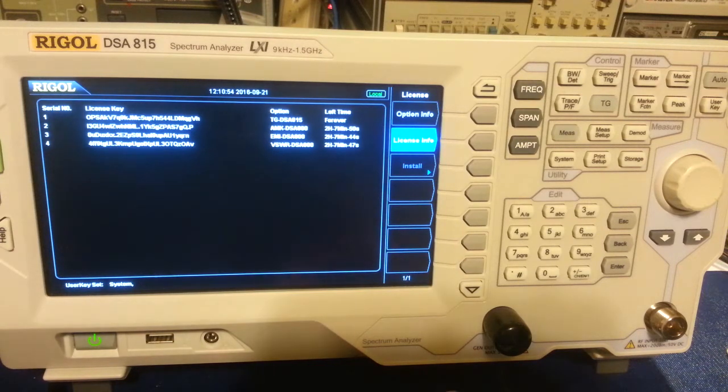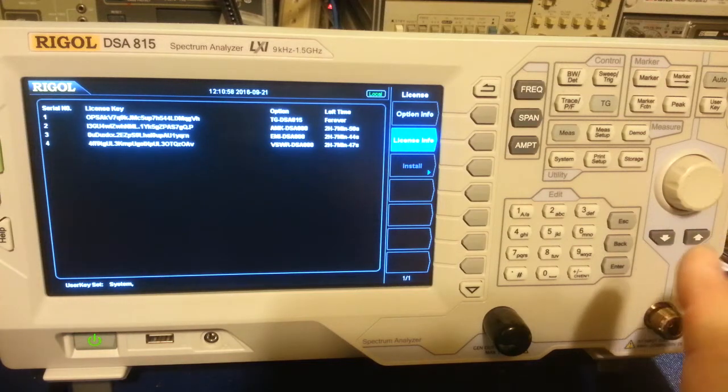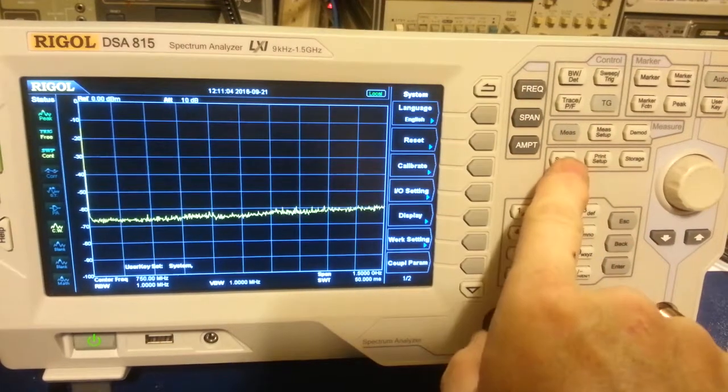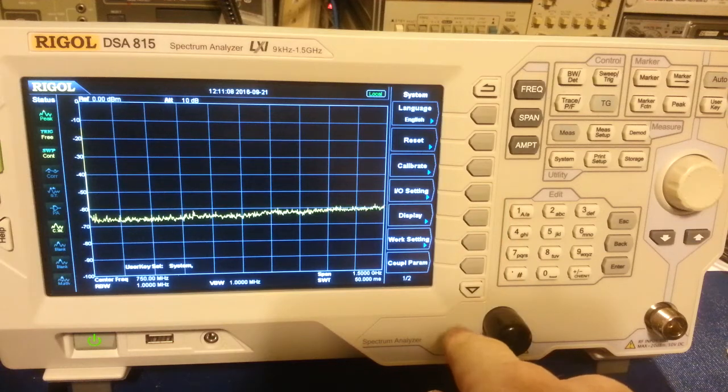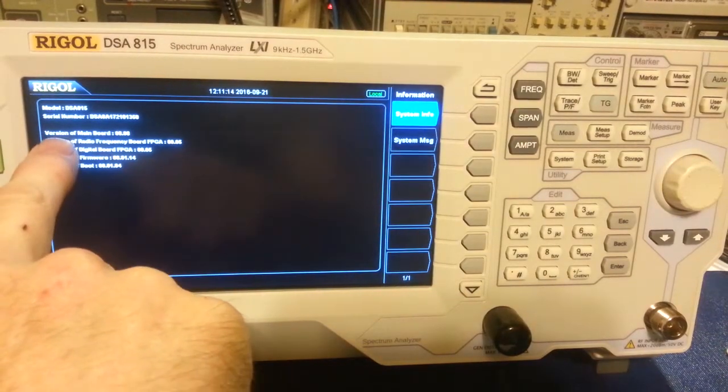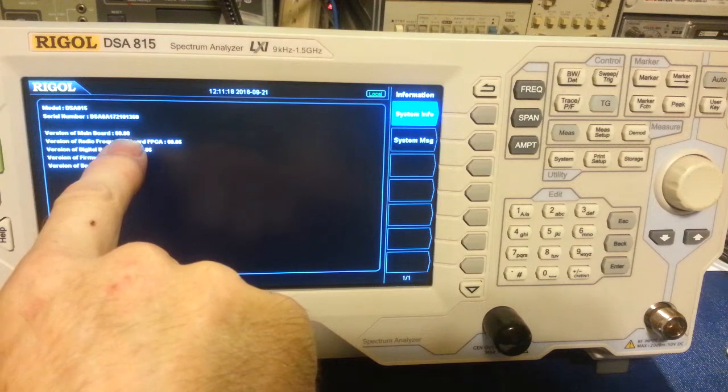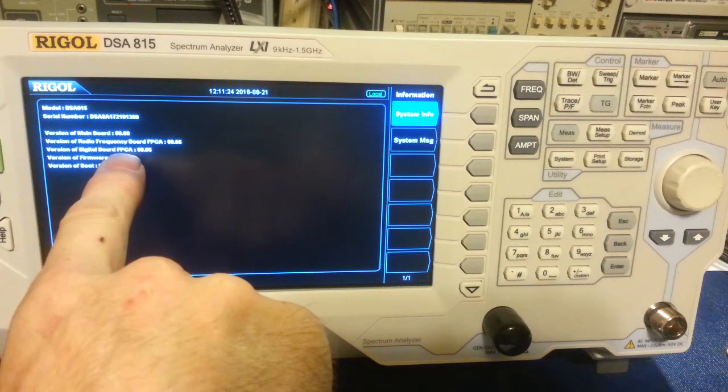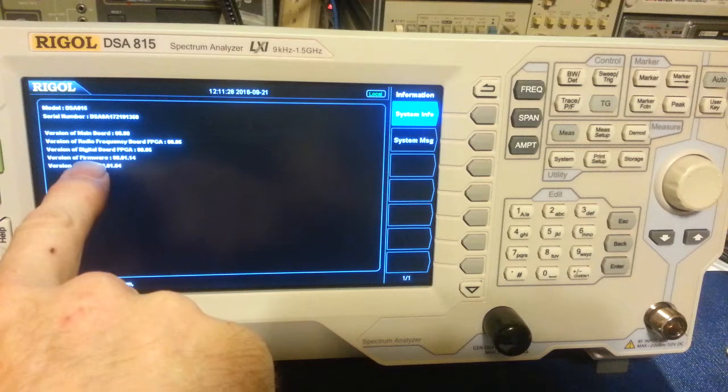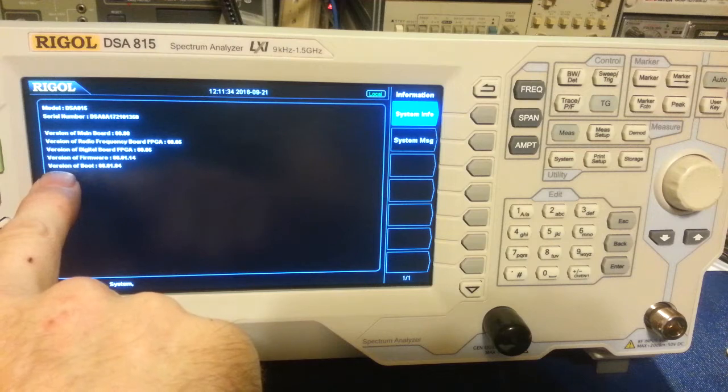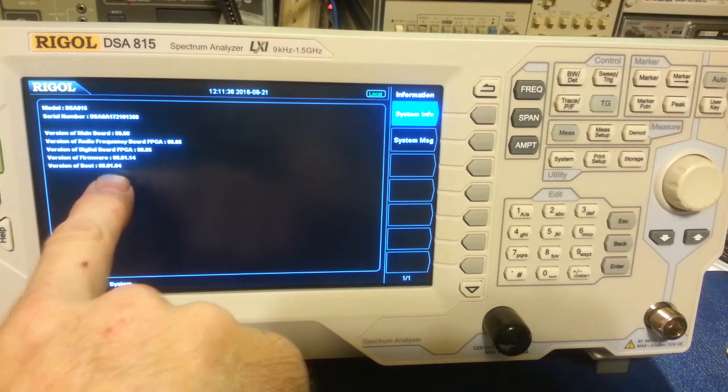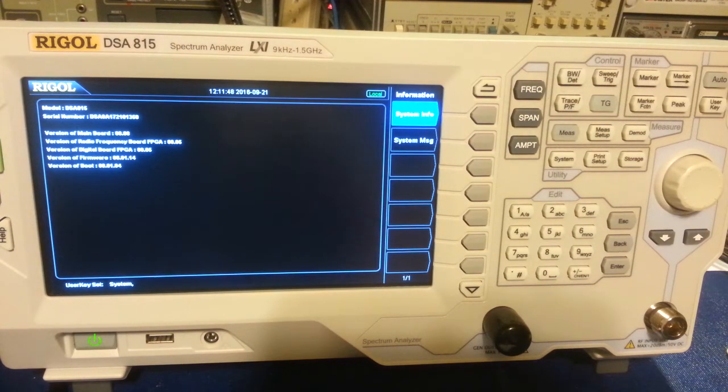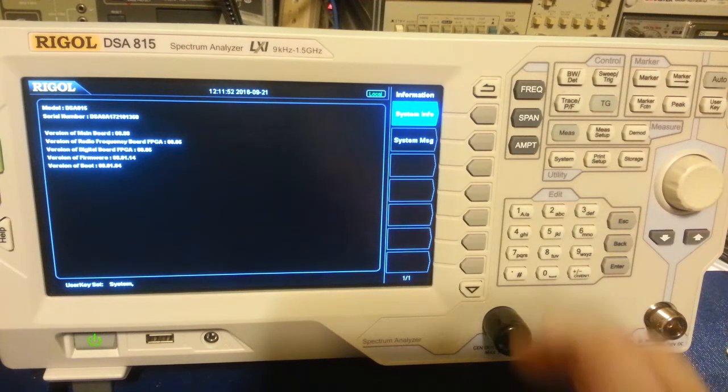So now I don't know if this works on the newer ones. Just so you know, this one is running, let's see, let's back out. System. Information. Okay so this is running main board double-aught 0.08, RF board FPGA is double-aught 0.05, the digital board FPGA is double-aught 0.05, the two important ones I guess are the firmware double-aught 0.01.14, and the version of boot or the boot version is double-aught 0.01.04, because I've had this for quite some time. So they probably, actually I should probably go online and see if they have updated, any updated software for it. I really don't need it because I've never had any bugs, I've never run into any issues with this.